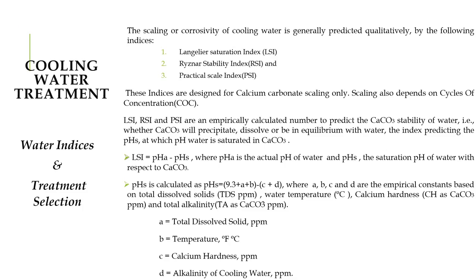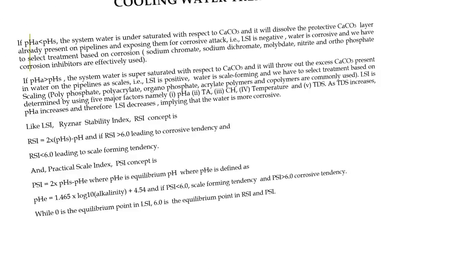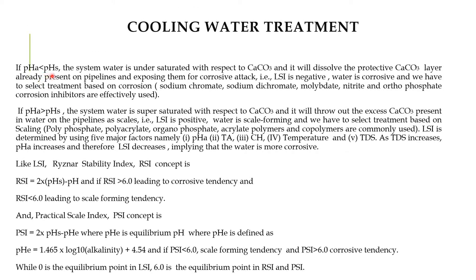If pH actual is less than pH saturated, the water is undersaturated with respect to calcium carbonate. It will dissolve the protective calcium carbonate layer already present on pipelines, exposing them to corrosive attack. A negative LSI means water is corrosive, and treatment should be selected based on corrosion control — sodium chromate, sodium dichromate, molybdate, nitrite, and orthophosphate corrosion inhibitors are effectively used.